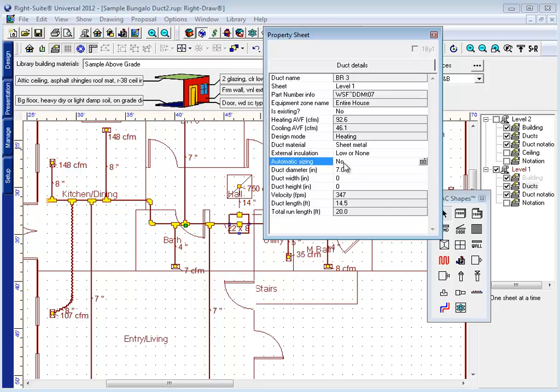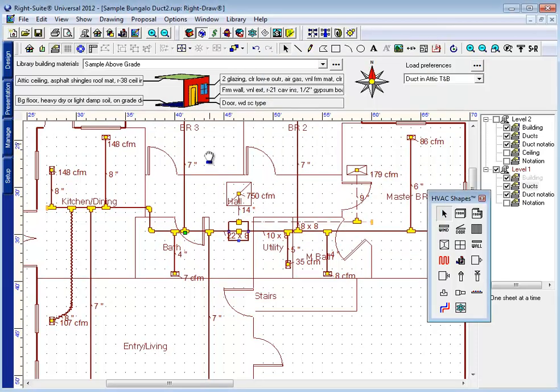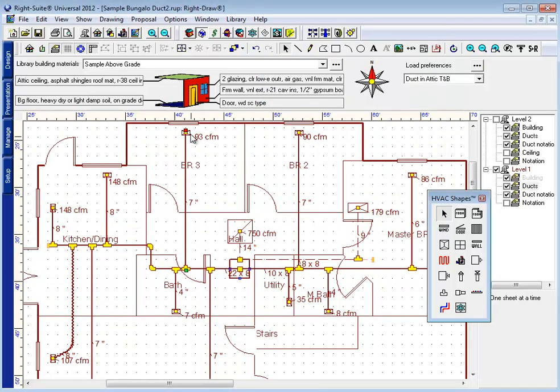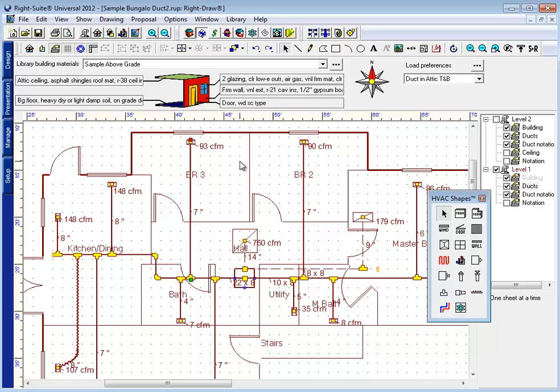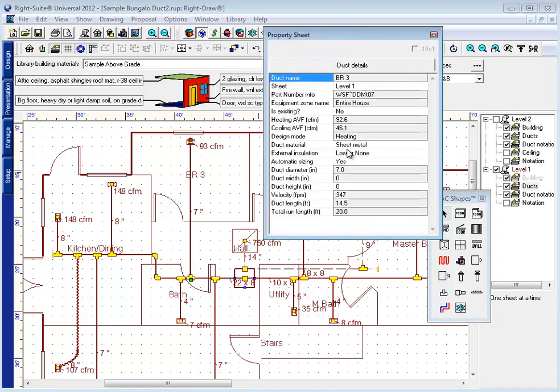Now this can come in handy in a few situations. For example, if I wanted to run a duct that started off as sheet metal but ended as flex, there are a couple things I can do. First, it should be noted that if you're not using Wrightsoft's materials list, determining how you want to size that duct as a sheet metal duct or as a flex duct might determine how you want to do this. In other words, if you're just doing five foot flex ends and you're going to size that run as if it were a flex duct, then changing the entire duct to flex wouldn't change anything about your design.